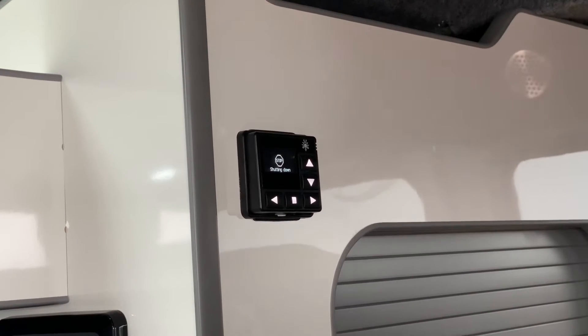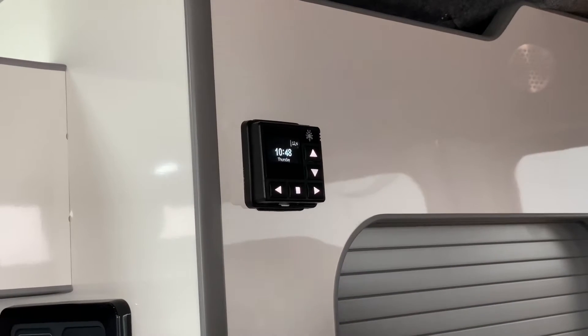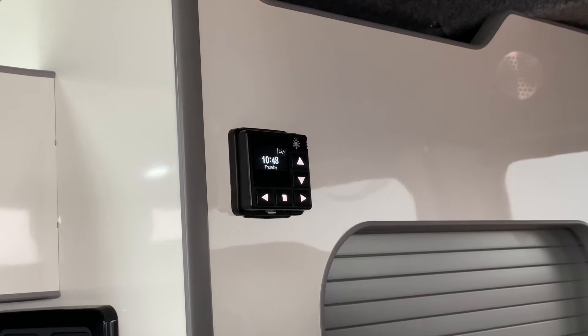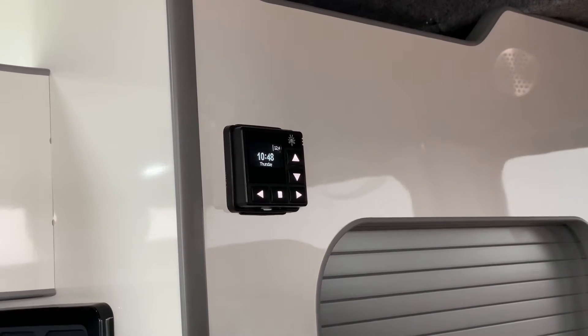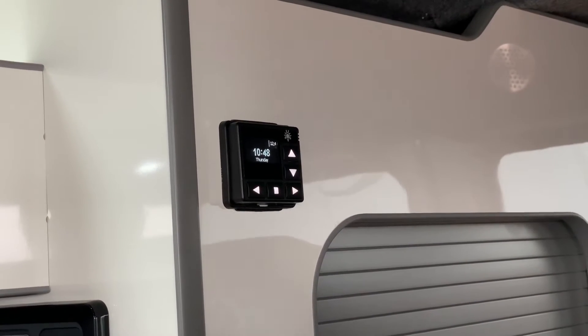It's very important to note that at least every 30 days you need to run your diesel heater up for 30 minutes.